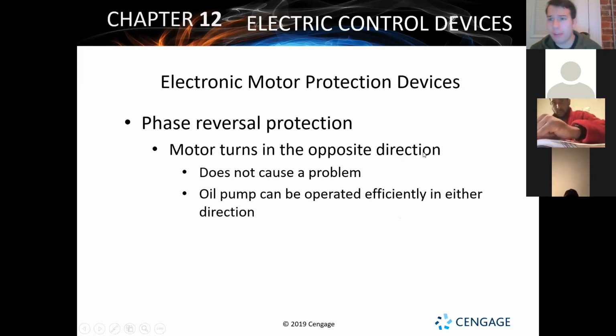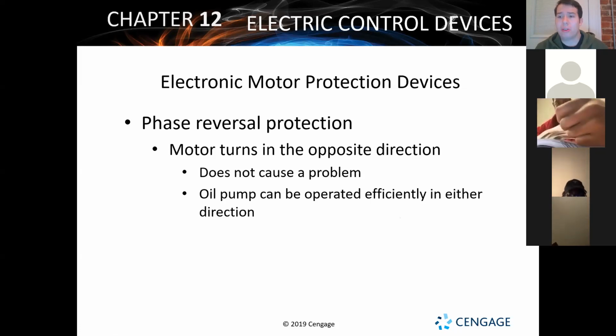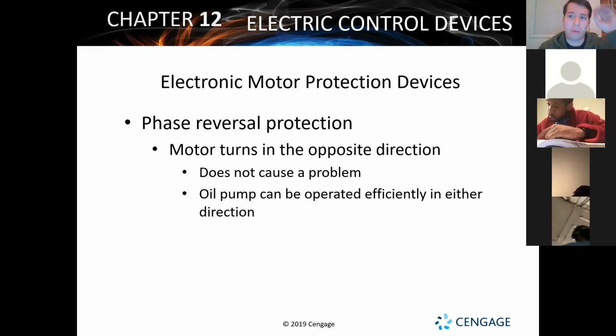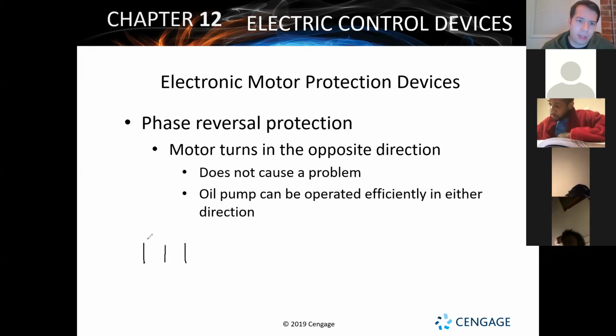So phase reversal, this is the other problem that can occur with three-phase electricity. When you all learn about three-phase motors a little bit more, you'll learn that how you wire up a three-phase motor, and which phase is wired to which leg of the motor, can actually affect its rotation. So let's say I have my motor, and I've got leg 1, leg 2, leg 3, and they're hooked up to terminal 1, terminal 2, and terminal 3.